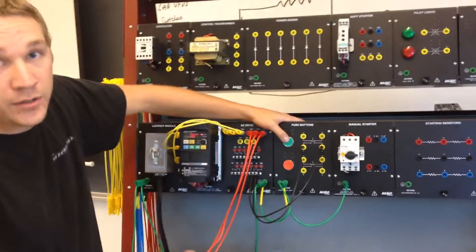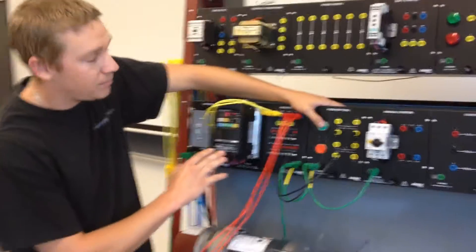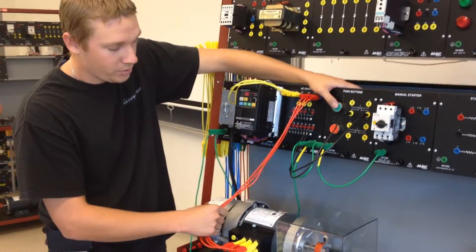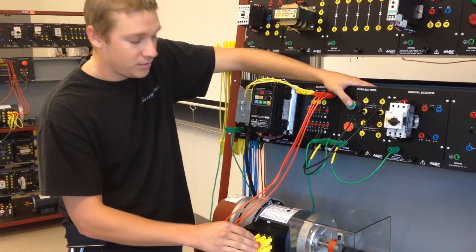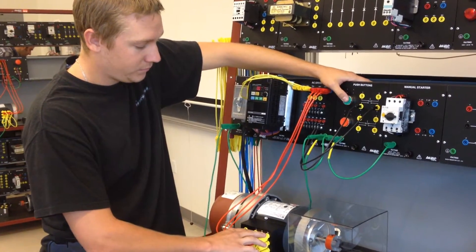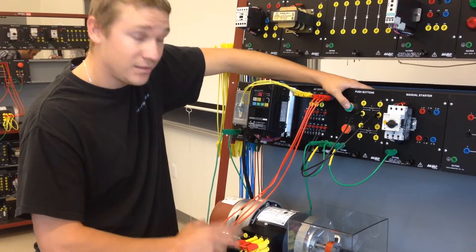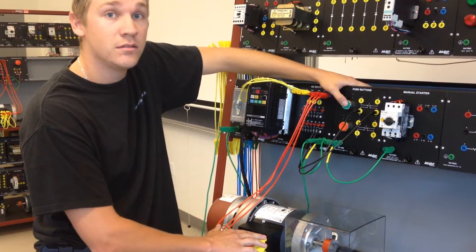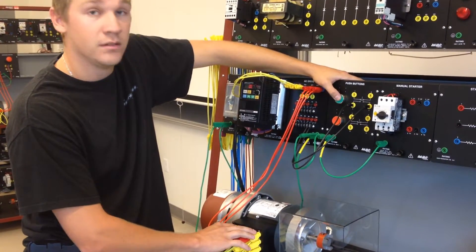When we push this push button, it will cut the AC power from the VFD going into the motor and supply DC voltage to the AC motor. This is a three phase motor. It supplies DC voltage to two of the three phases, and then on the other phase it's a negative to ground.